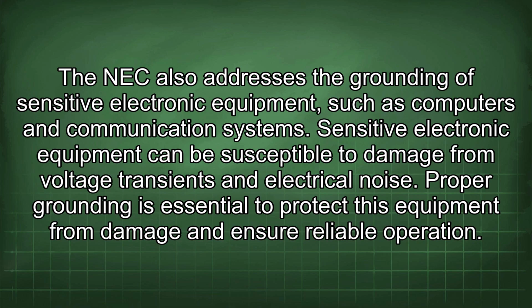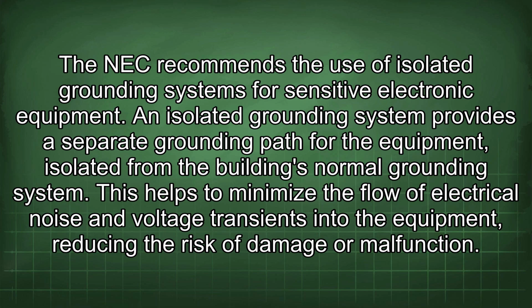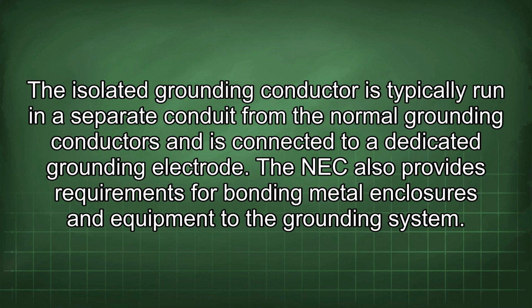The NEC also addresses the grounding of sensitive electronic equipment, such as computers and communication systems. Sensitive electronic equipment can be susceptible to damage from voltage transients and electrical noise. Proper grounding is essential to protect this equipment from damage and ensure reliable operation. The NEC recommends the use of isolated grounding systems for sensitive electronic equipment. An isolated grounding system provides a separate grounding path for the equipment, isolated from the building's normal grounding system. This helps to minimize the flow of electrical noise and voltage transients into the equipment, reducing the risk of damage or malfunction. The isolated grounding conductor is typically run in a separate conduit from the normal grounding conductors and is connected to a dedicated grounding electrode.